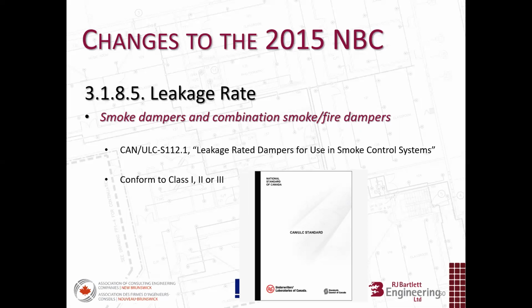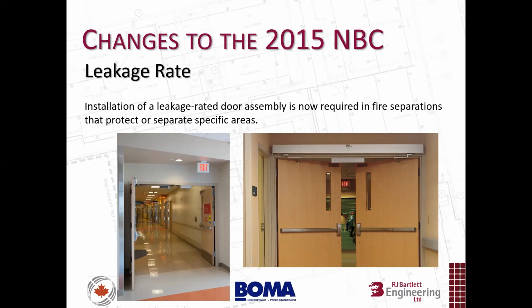So class 1 or 2 leakage rating to be used, or a smoke damper specified for that for their care type occupancies. But then another interesting component to that was that the majority of these smoke dampers do perform. We haven't really seen, or I haven't come across, a smoke damper that has a class 3. So I think achieving the class 1 or 2 is reasonably easy to achieve. So now we have some new requirements for leakage rate with respect to certain door assemblies. So installation of leakage rated door assembly is now required in fire separations in specific areas.